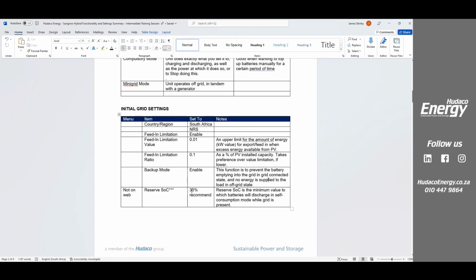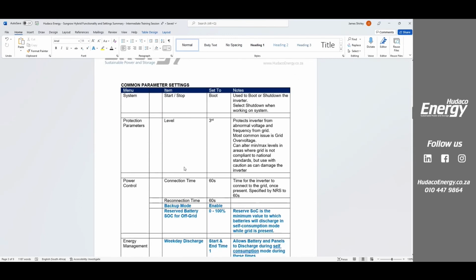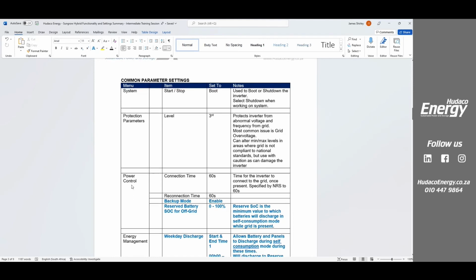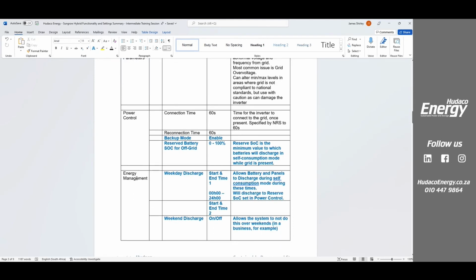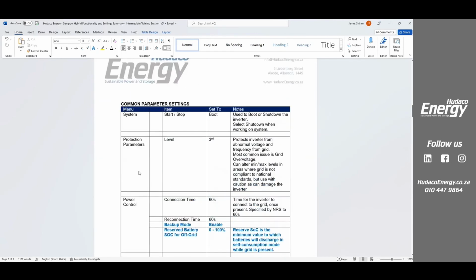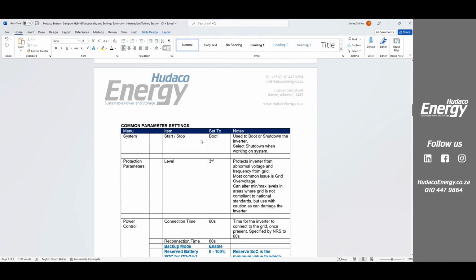We can also, through the reserve state of charge, tell it, well, don't heat my geyser so that if I've got load shedding at 8 o'clock, I'm going to have no power left. Okay, so that's the function of these two pieces here. All right, now we're going to go into the common parameter settings, and then the advanced parameter settings. What I'm going to talk about is only the items in blue. You'll see in the menu, when you go into the menu, there are different options that you can click. Those are here. Then in the menu path, as it goes down, this is your next setting. When you click on that, here's what you can set, or an option that we say you should set it to, and then some notes to say, well, this is what it actually does.